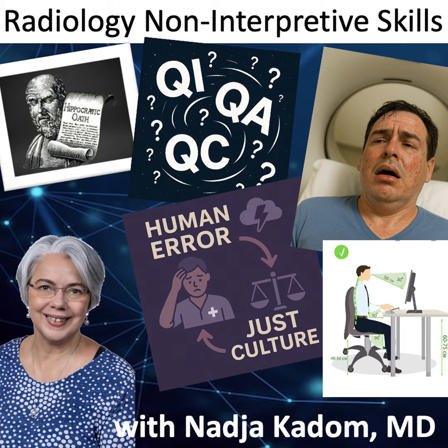Now the newer scanners, which is really neat, go from having about 1,700 liters of liquid helium, which is what a lot of the scanners have, to about 7. Wow, which is just mind-boggling. And now there are even some where you can do an inside quench, where you quench it but it stays within so that it doesn't expel all of it, and it's just for a couple of minutes or hours, and then you can continue on with scanning.